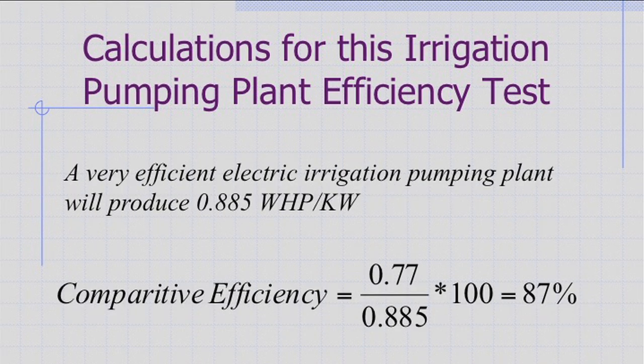Then we compare that against what we would expect from a very efficient electric irrigation pumping plant, which will produce about 0.885 water horsepower per kilowatt. So if I take our 0.77 divided by 0.885, I get 87%. And that's compared to a very efficient electric irrigation pumping plant. This isn't something that has to be done every month. It only has to be done once a year or once every other year. But it's a worthwhile way to check how well your pump is pumping water and how efficiently it's using power.